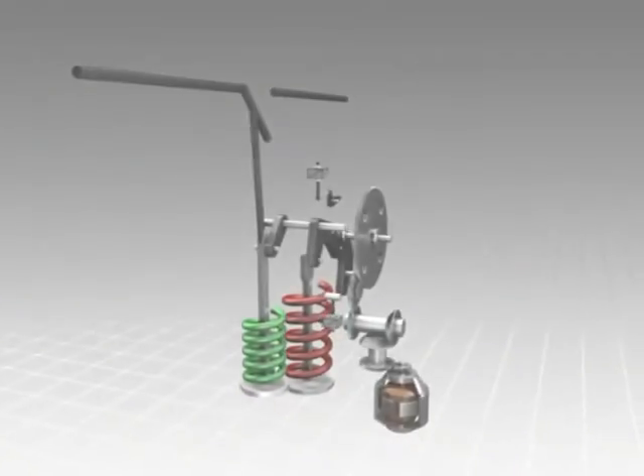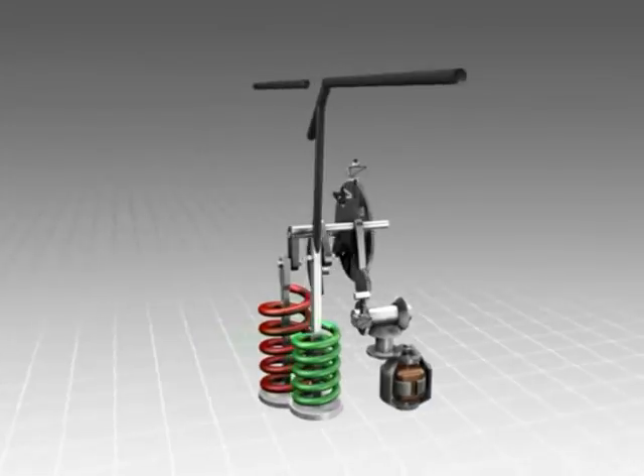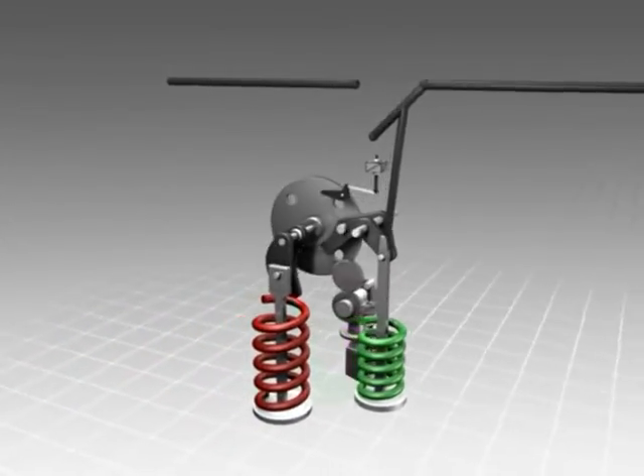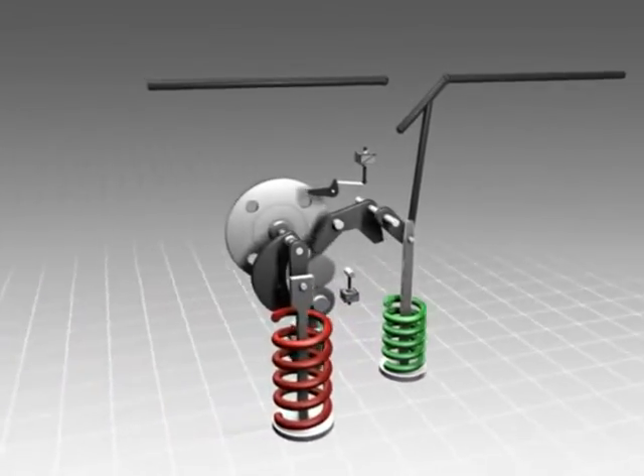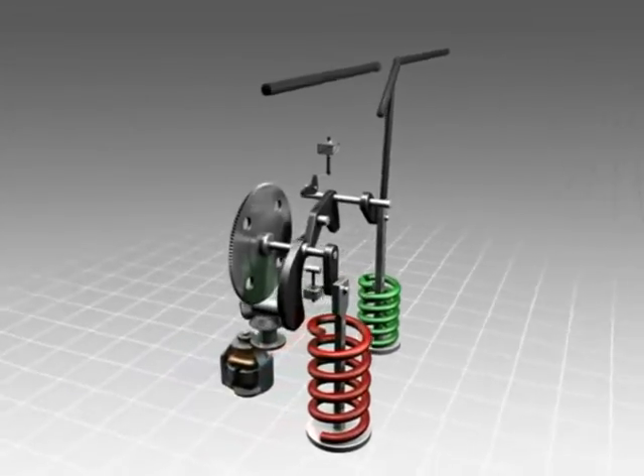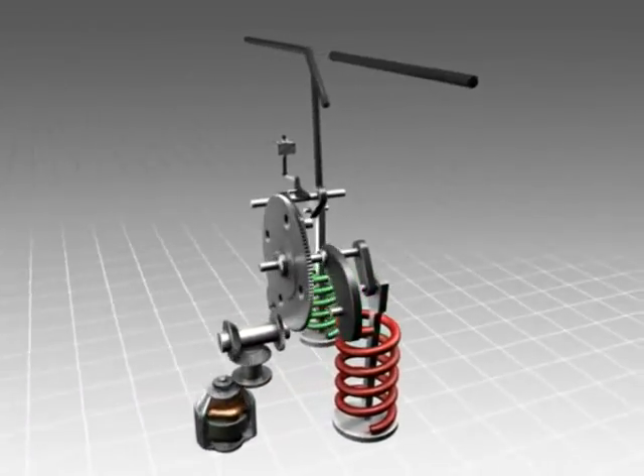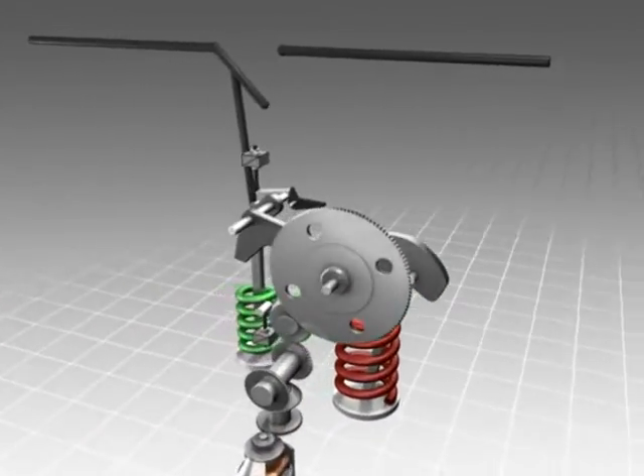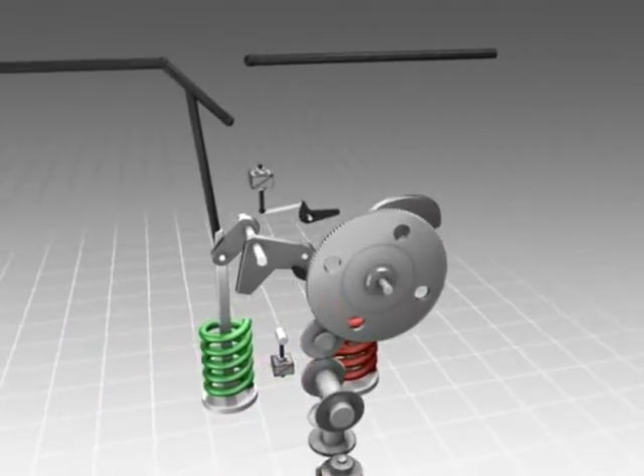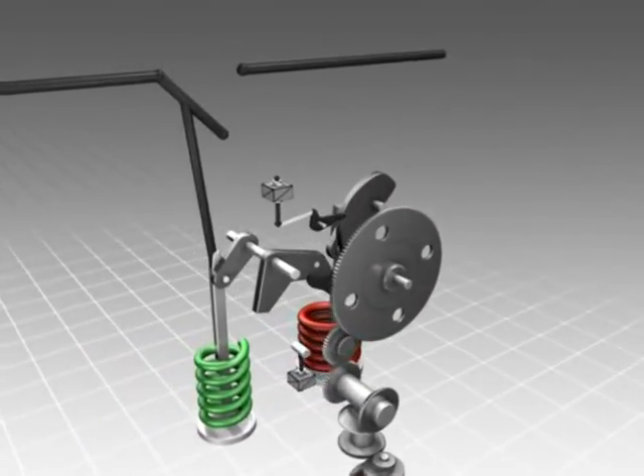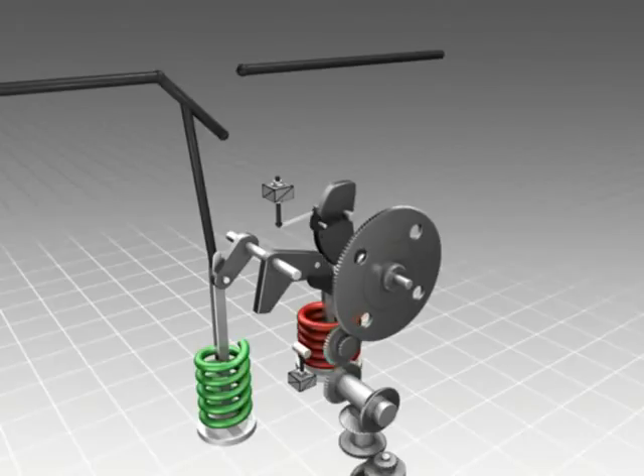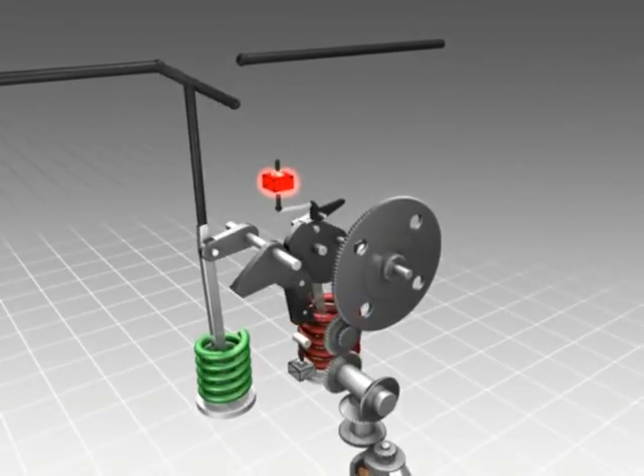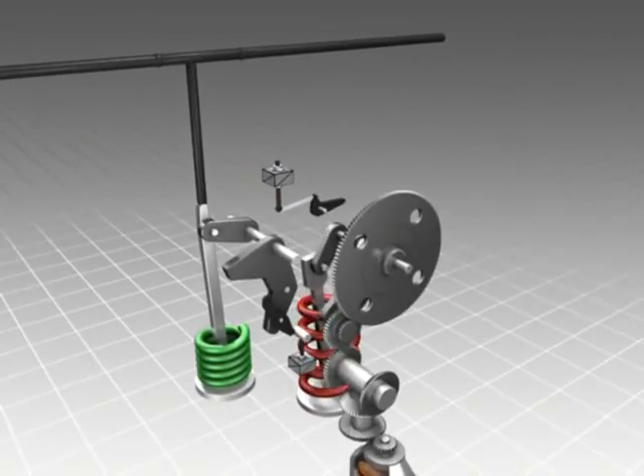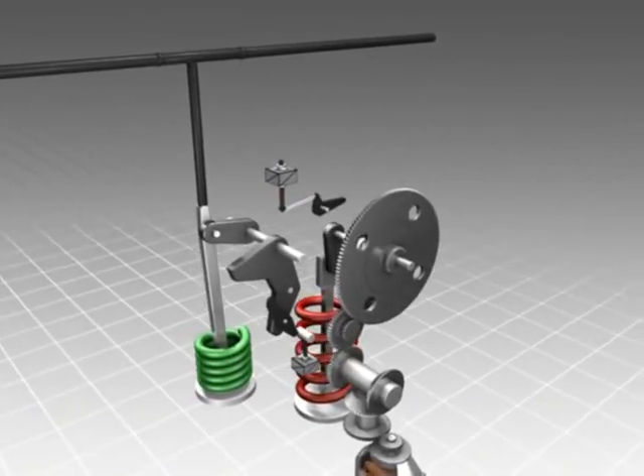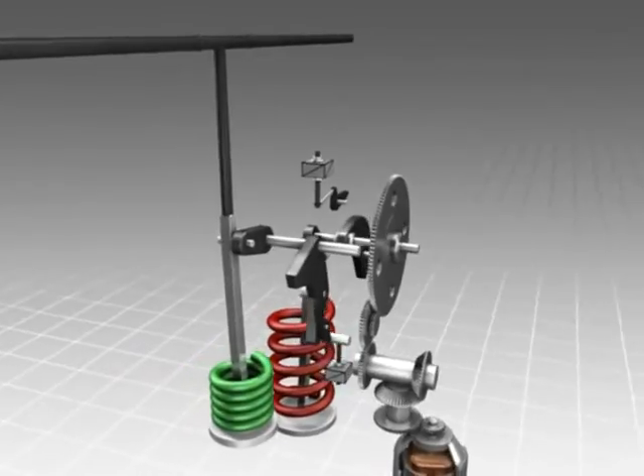The compact spring-stored energy operating mechanism provides the force for opening and closing the circuit breaker. It is installed in a corrosion-free aluminum housing and completely isolated from the gas compartments. Roller bearings, the maintenance-free spring mechanism, and a small number of moving parts ensure decades of reliable operation. The positions of the closing and the opening spring are clearly visible in the operation mechanism cubicle.